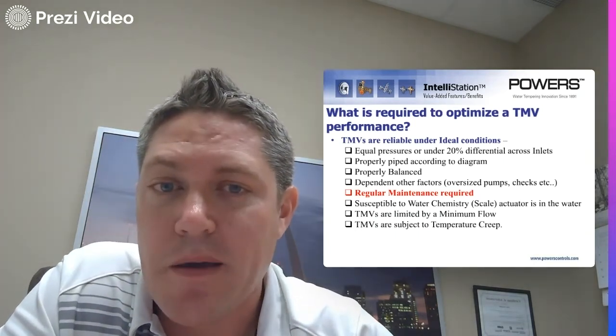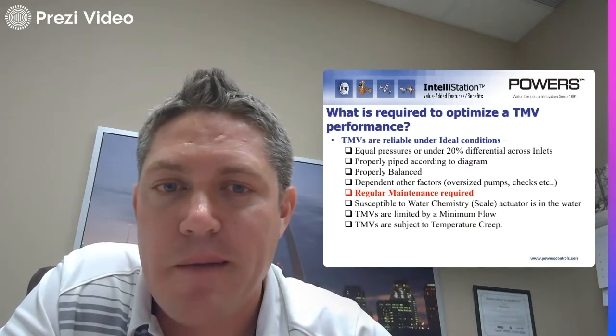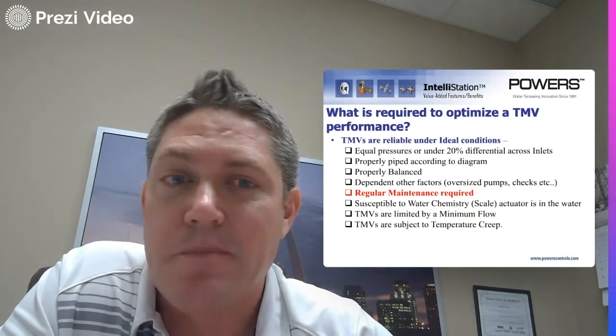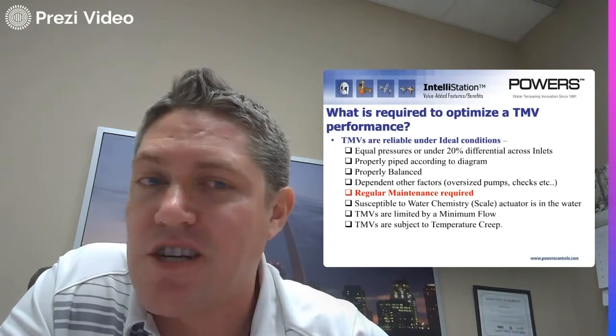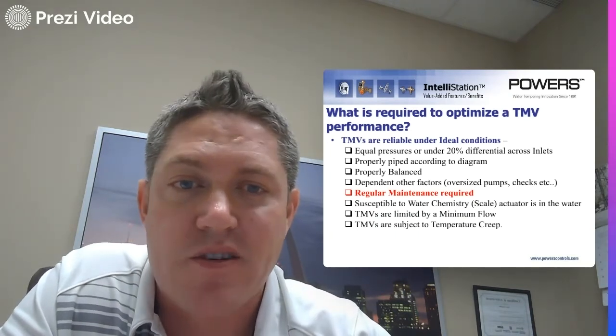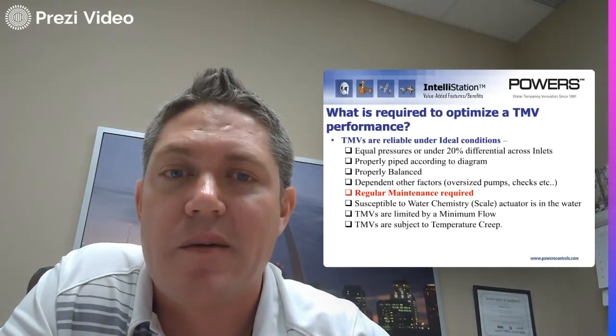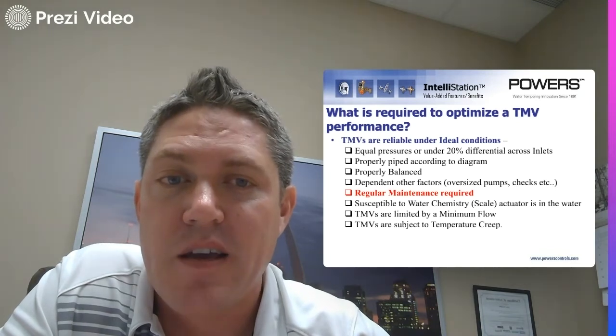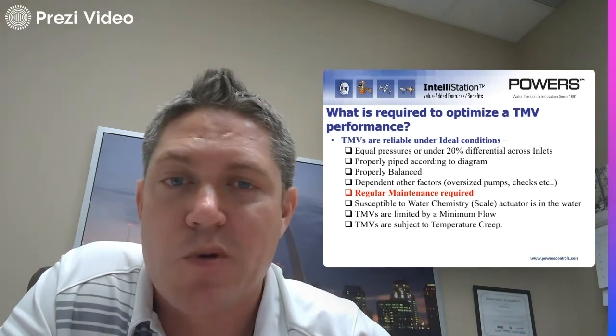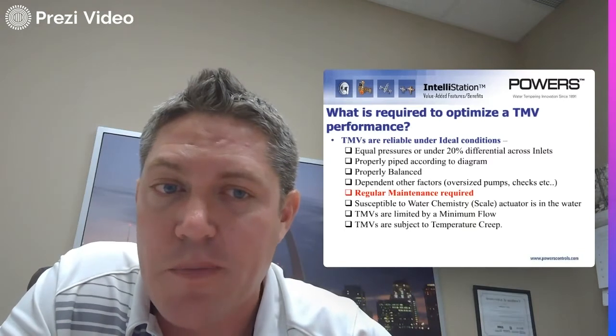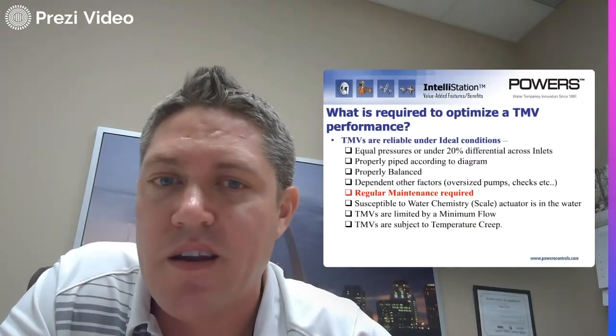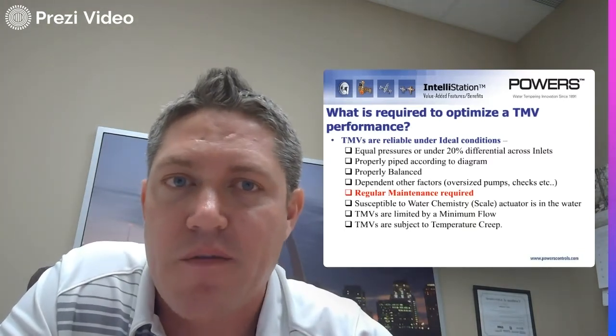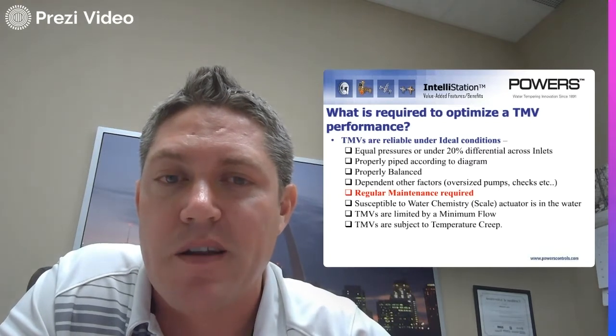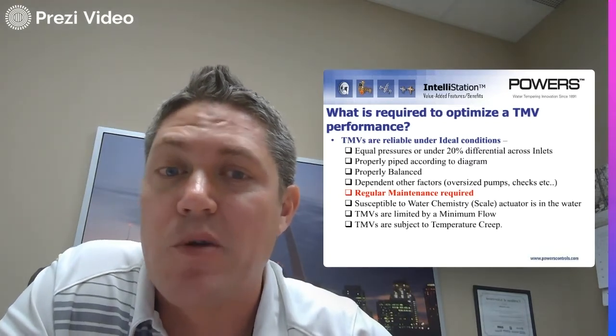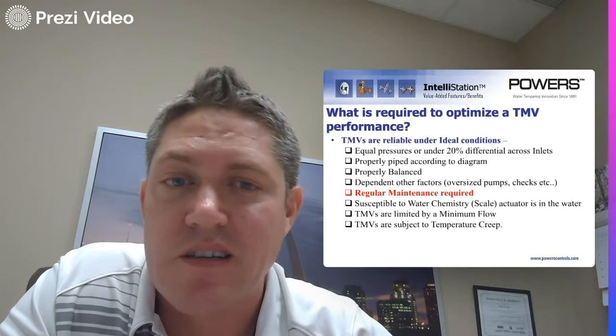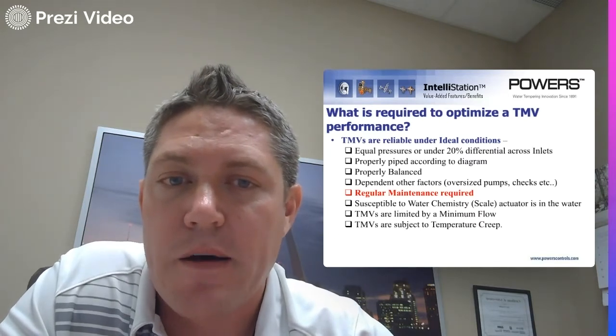So that all needs to be properly balanced and properly piped. Oversizing pumps, not having check valves in the right spot. These are problems that will cause a thermostatic mixing valve to not function properly. And regular maintenance is required. They're susceptible to scale buildup. That's the number one reason that a thermostatic mixing valve fails, is that it gets scaled up and then it needs to be rebuilt, parts taken out, descaled, and so forth.